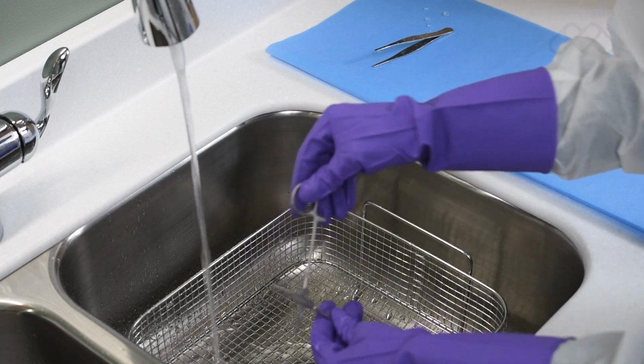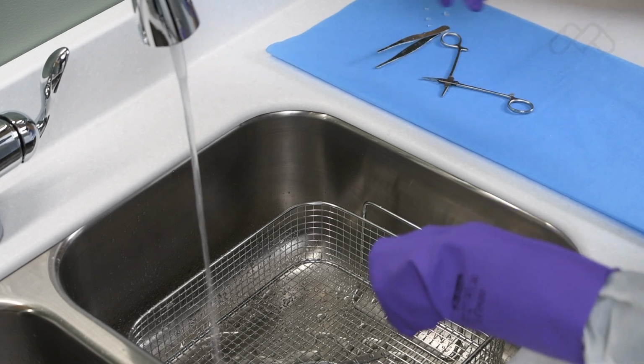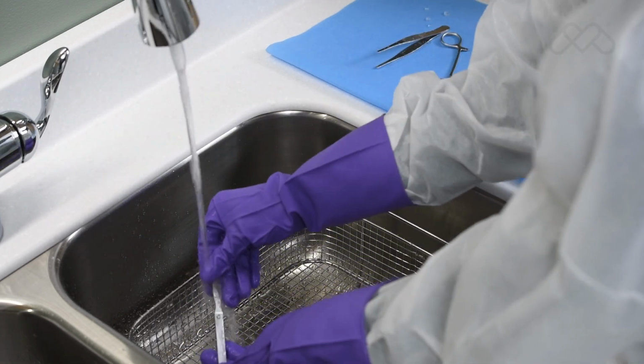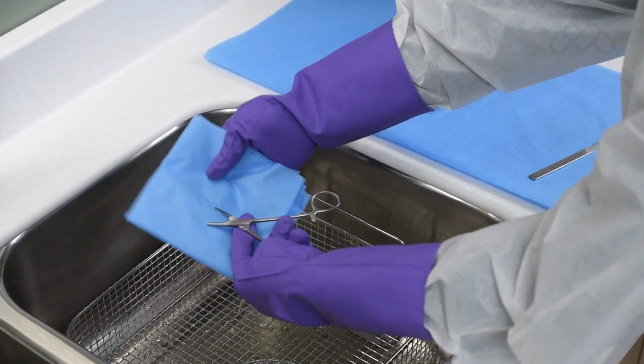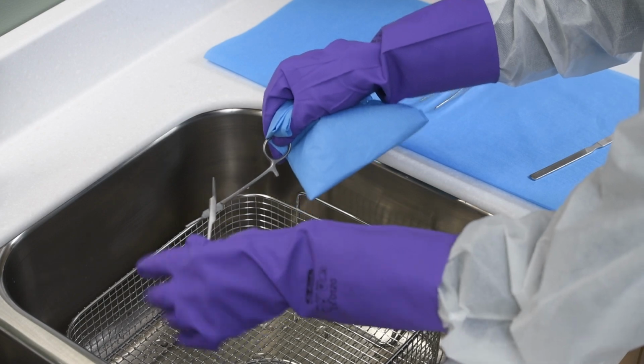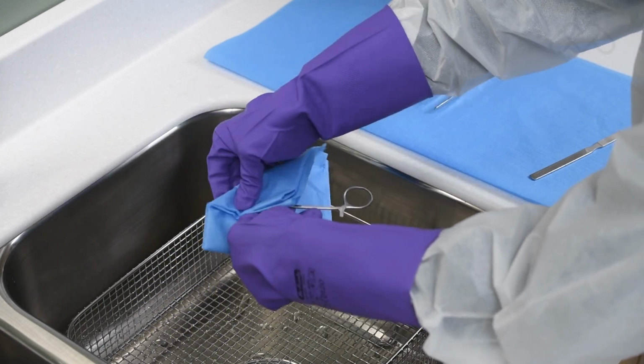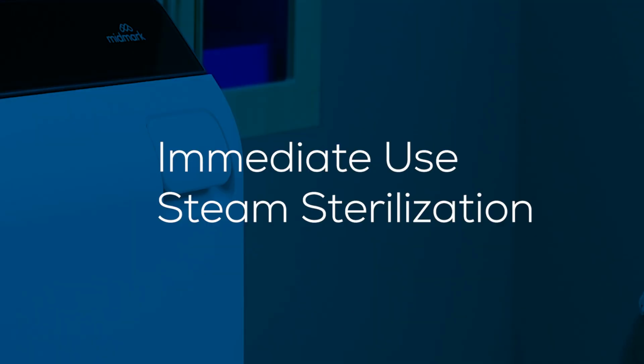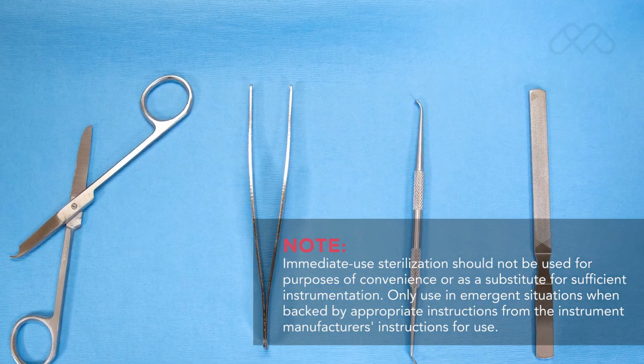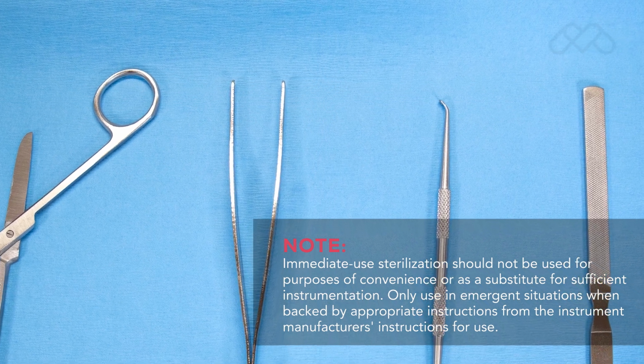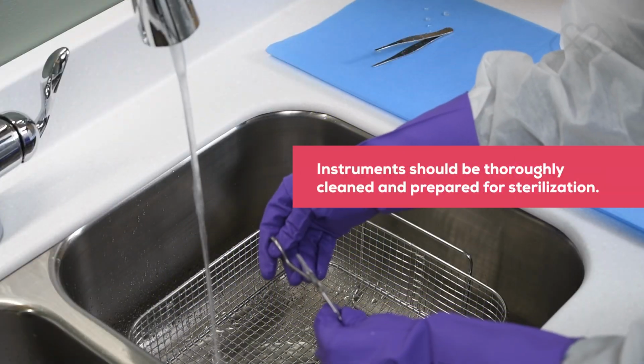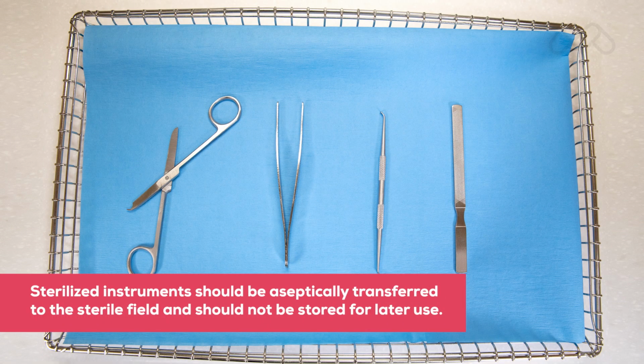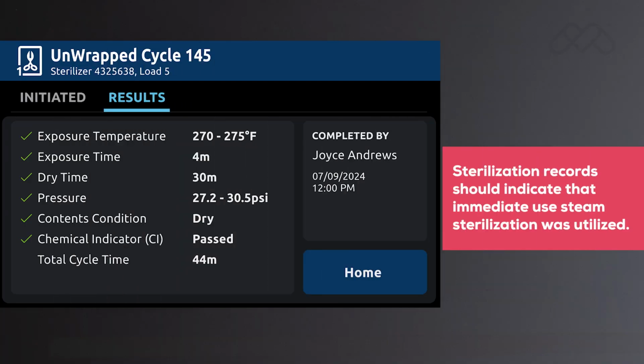When rinsing is complete, instruments should be inspected for damage, debris, and detergent residue, and dried before packaging. If necessary, repeat the cleaning process. If the instrument manufacturer's instructions require lubrication of the instruments after cleaning, wipe off excess lubricant before packing for sterilization or loading into the sterilizer. Immediate use steam sterilization. In urgent clinical situations, Midmark steam sterilizers are capable of immediate use steam sterilization of instruments. Instruments should be thoroughly cleaned and prepared for sterilization. Instruments sterilized for immediate use should be aseptically transferred to the sterile field and should not be stored for later use. Sterilization records should indicate that immediate use steam sterilization was utilized.